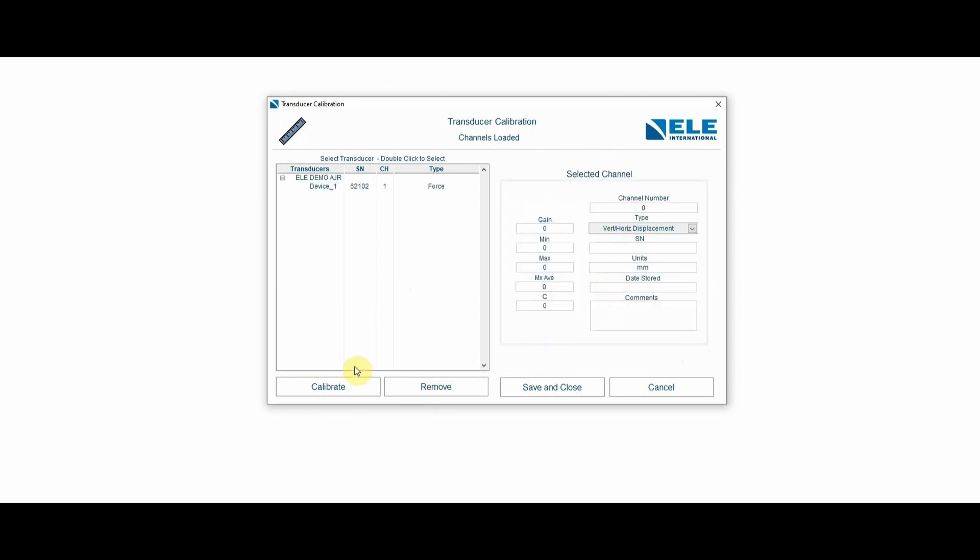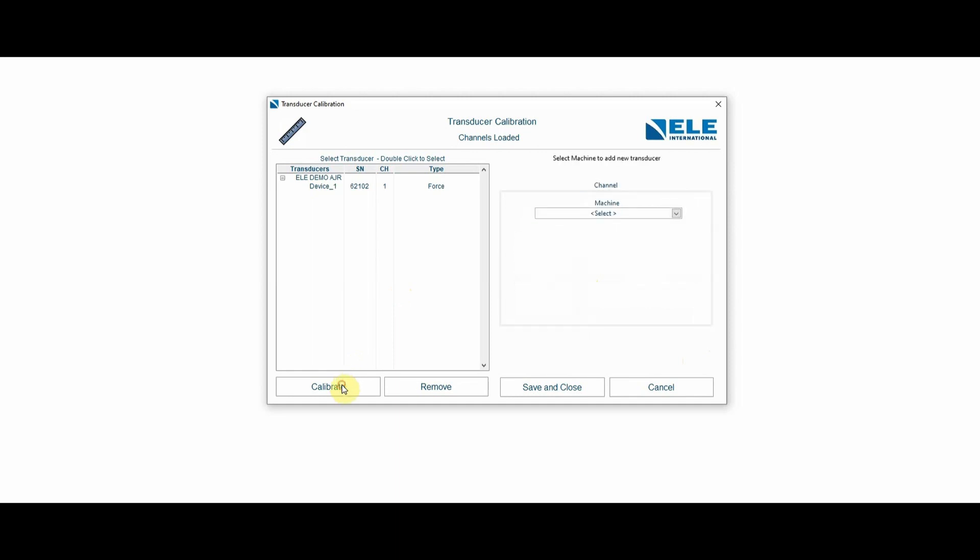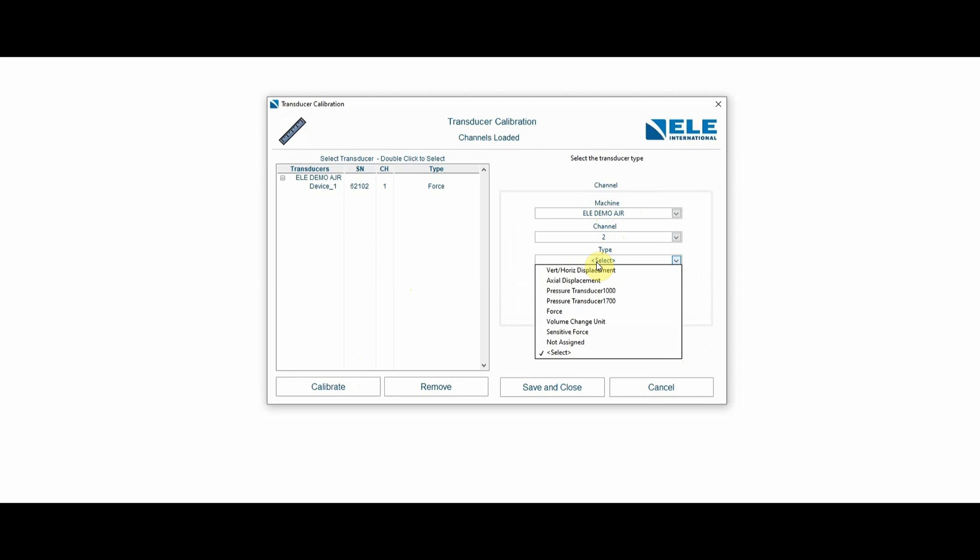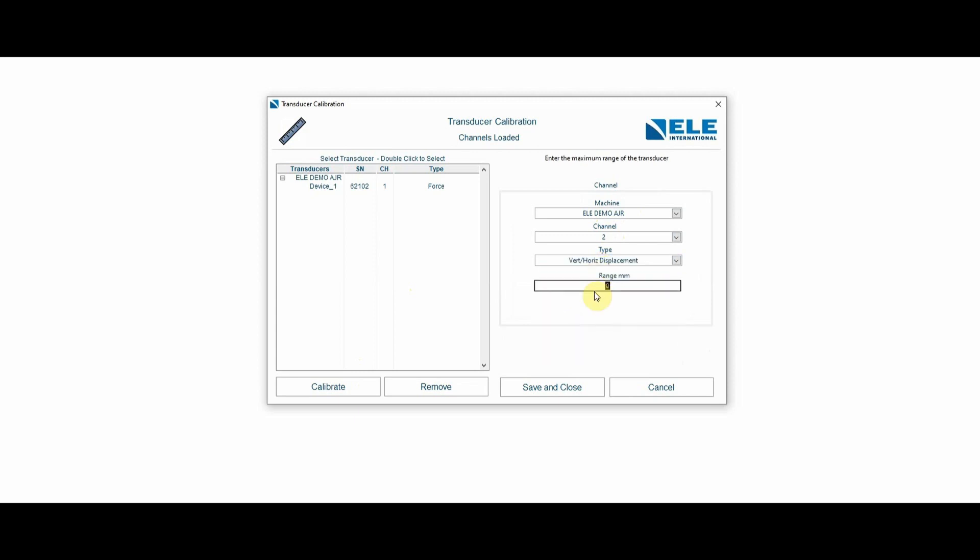What I'm going to do next is enter another transducer. So I'm going to set up another transducer for the ELE demo AJR machine. This is going to be channel number two, and this is going to be my vertical horizontal deformation or displacement transducer, which has a range of 15 millimeters.